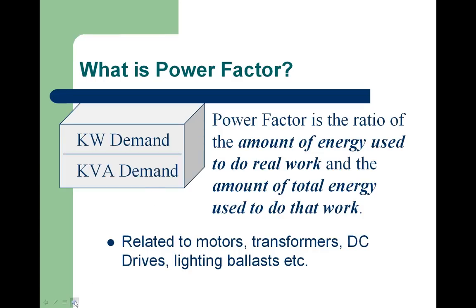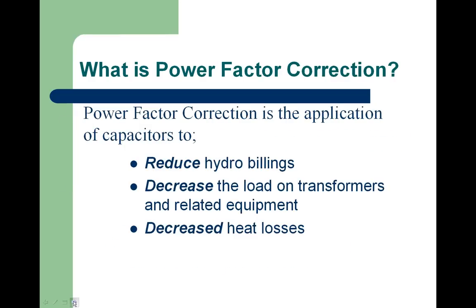So what do we use power factor correction for? Generally, probably 95 to 99% of the time, power factor correction is used to reduce the hydro demand charges on the hydro bill. We'll get to what the percentages are, but basically in Ontario, sites pay power factor penalties on power factors less than 90%, except in Toronto. Toronto has a different rate structure, billed on kilowatts separately from kVA, so Toronto actually has a unity power factor.